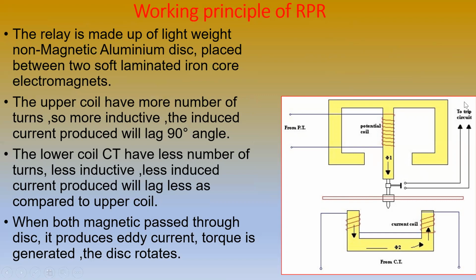Because they design it with more turns, more inductive, the inductive current produced will lag by 90 degrees. The lower coil is the current coil. It has fewer turns, so it is less inductive, and the current is produced with less lag as compared to the upper coil. This induced current in the coil will produce magnetic flux. The magnetic flux will link through the disc, and this will produce an eddy current in the disc. This eddy current will generate a torque, and the disc starts to rotate. This is a stopper button that will stop it, and it does not allow the disc to connect with the trip circuit.